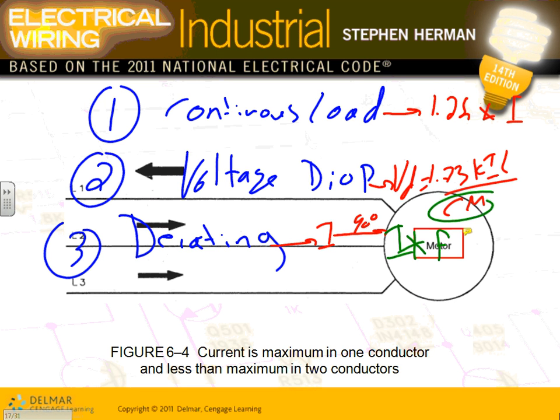Okay, Chris, I have three sizes. Which size should I use then? See, I did a calculation for a load. I have three sizes. Let's just take an example. This gave me a 4-aught. This one gave me 2-aught, and this gave me 1-aught. Which conductor should you use? Was the voltage drop at the continuous load? No, not at the continuous load.